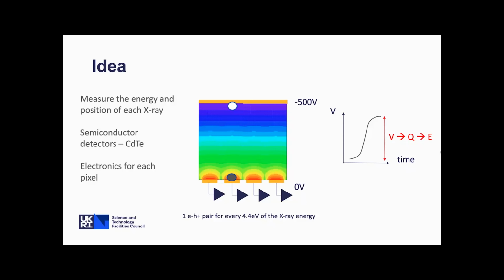We apply a bias across the detector. So this is typically 500 volts for a 1 millimeter thick cadmium telluride detector, which generates this electric field. And then when an X-ray comes in, it generates electron and hole pairs. So for every 4.4 eV of the X-ray, we get 1 electron hole pair. So a 44 keV photon is going to give us 10,000 electron hole pairs in a charge cloud.